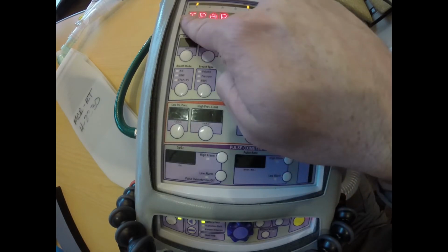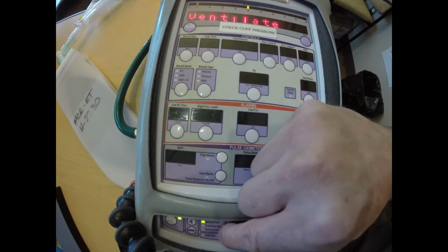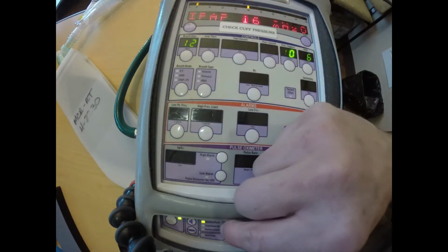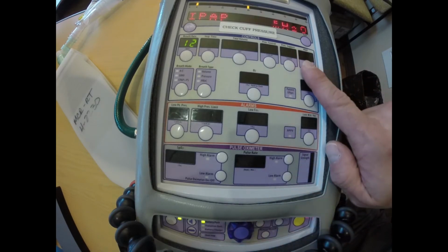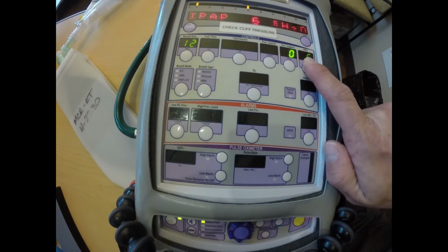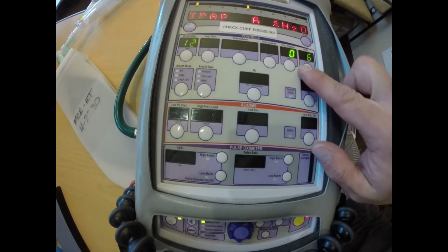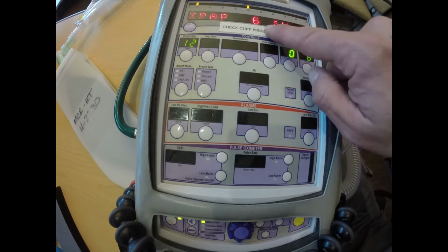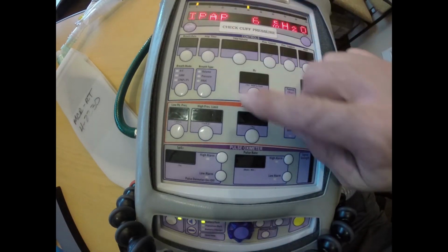When I select that, it gives me a menu to adjust my inspiratory positive airway pressure. I don't want to do that because I'm choosing to use CPAP and or CPAP plus pressure support. So I'm going to select my IPAP and dial that down to the lowest level, which will be 6. You'll notice that it's blinking right here. Pressure support plus PEEP is my inspiratory positive airway pressure. So 6 plus 0 is 6, and that's okay.